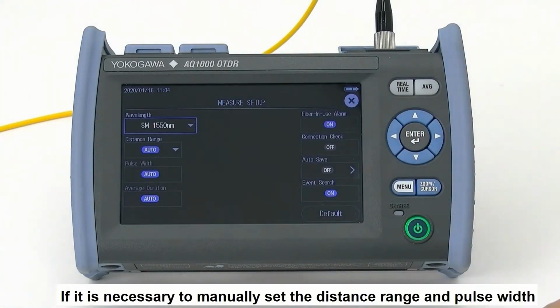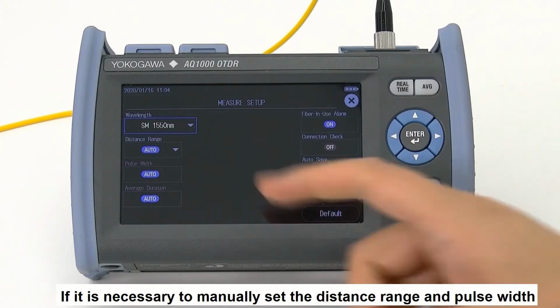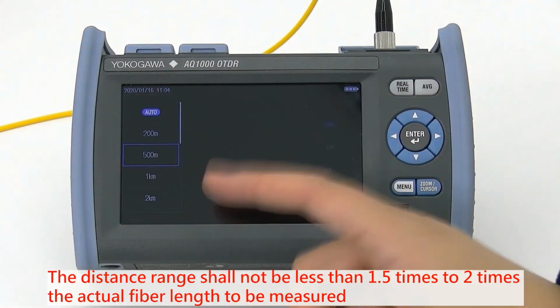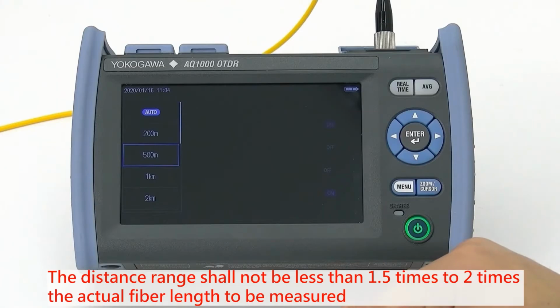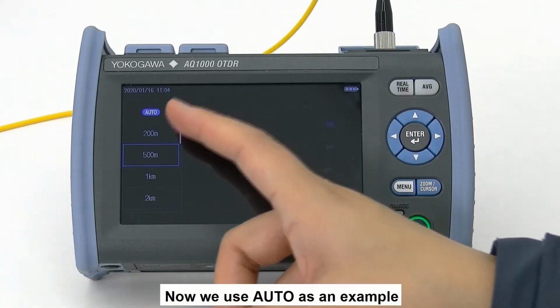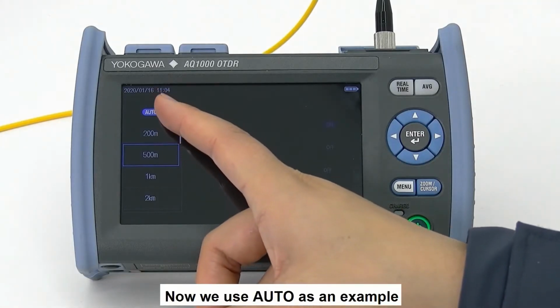If necessary, you can manually set the distance range and the pulse width. The distance range should not be less than 1.5 to 2 times the actual fiber length for the measurement. Now we use auto as an example.